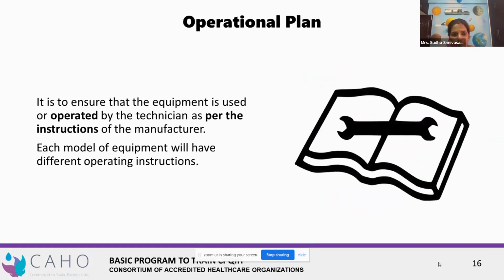Then what is an operational plan? It is to ensure that the equipment is operated by the technician or the user as per the instructions of the manufacturer. It's nothing but your SOP, listed out and made available next to the equipments inside the hospital. It has to be as per the manufacturer's recommendations. The same ventilator could have multiple models, and the operating methodology could be different for each. Maybe you have a new nurse who does not know how to operate. In case of an emergency, if she has to operate, there has to be an operating manual, a list of protocols, available next to the equipment, isn't it?